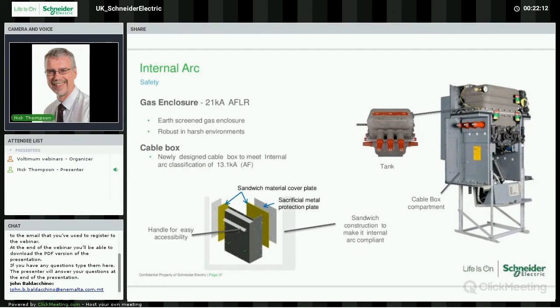Now, inside the cable boxes, we've got additional construction features to make sure it passes the internal arc testing. And we've got sandwich arrangements inside the cable box. One is a sacrificial plate that is designed to be deployed, and then the arc would stop at the sandwich material, which is an insulation material, and with the 1 second test which it's been tested to, it would then cease. Inside the cable boxes and also inside the gas enclosure, there are blast points or pressure relief points in the form of flaps in the cable box and a blast plate on the gas enclosure.